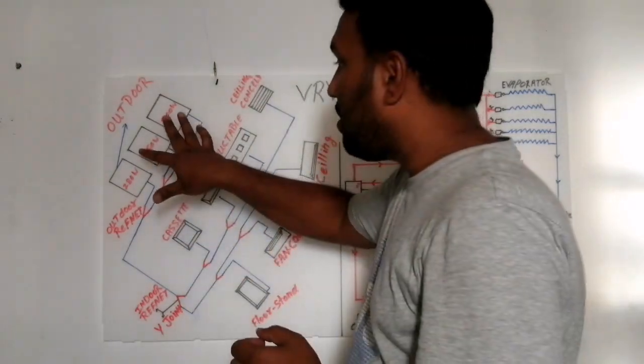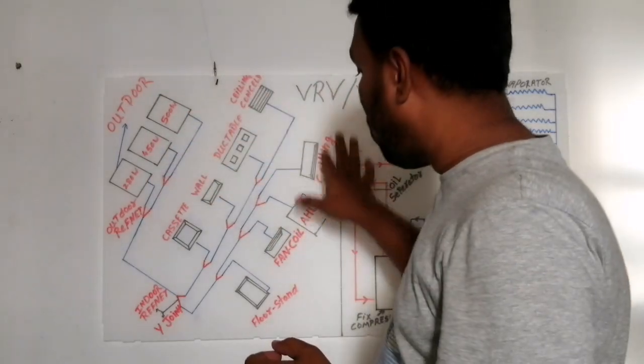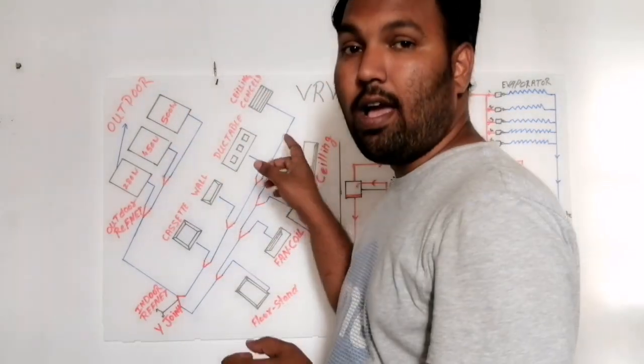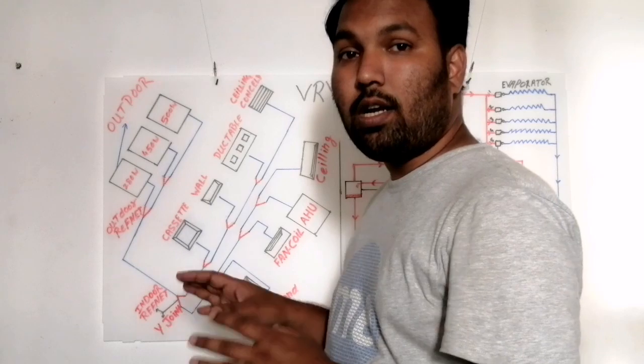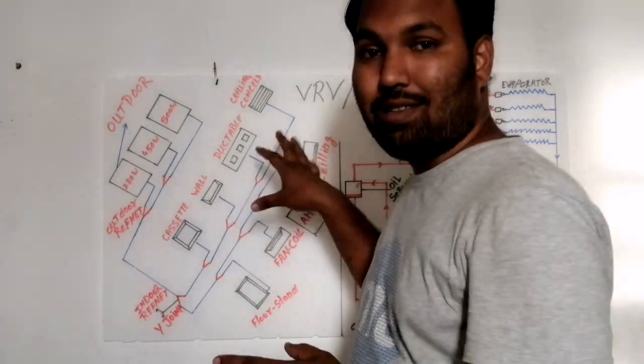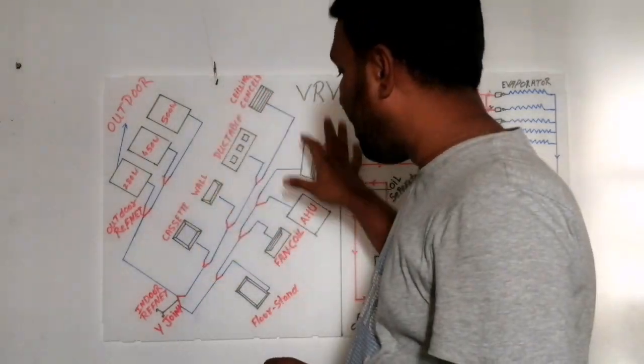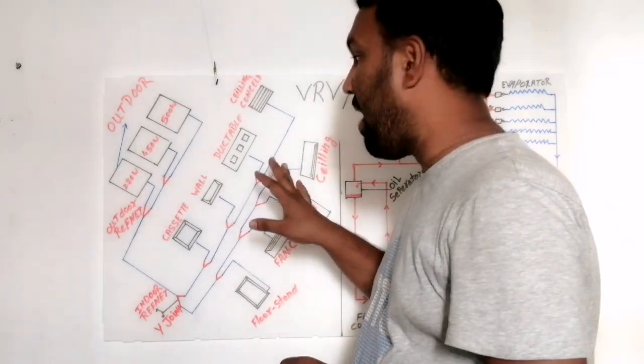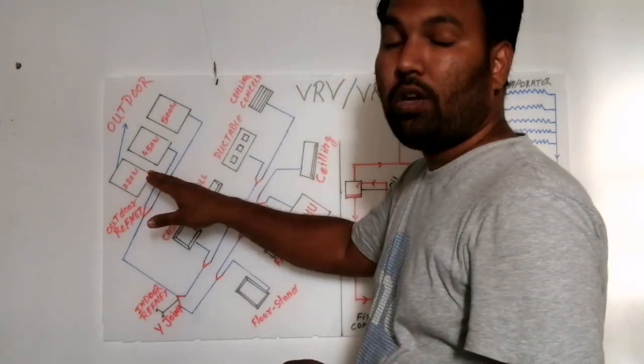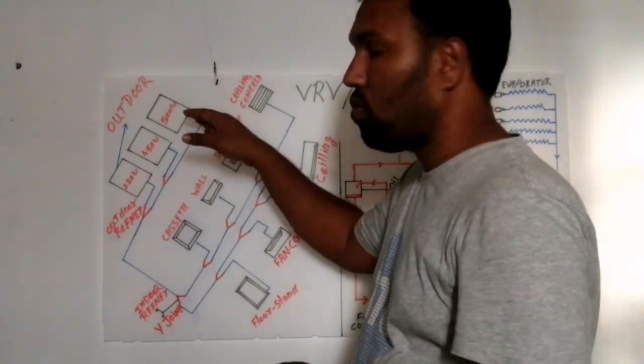When all these three compressors are working and the temperature inside has reached the certain temperature we have set, if our inside temperature has reached the goal, slowly our master unit will give a command to all the other compressors to slow down.